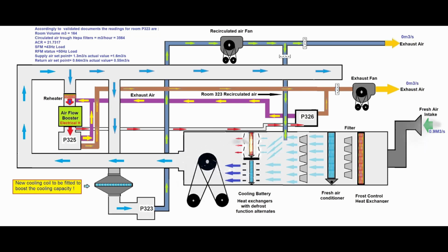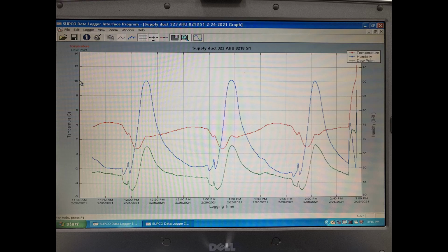on minus 15 degrees. Now when the coil which goes on defrost reaches 60 degrees and you melt the ice, the liquid, the water, will convert to steam and it will leak onto the cold chamber, and then I will have an average temperature which is not good.